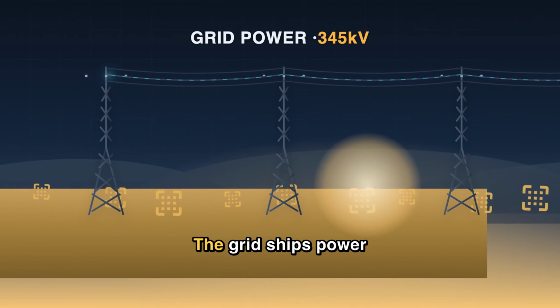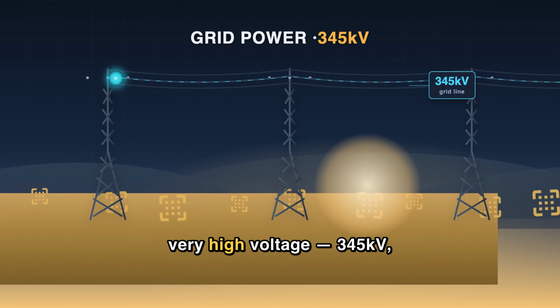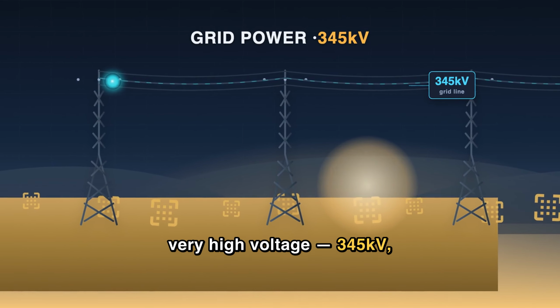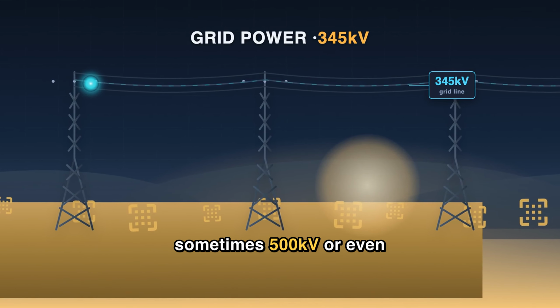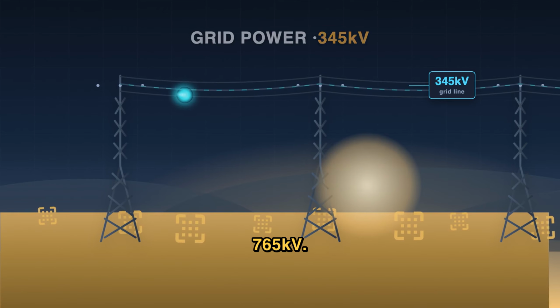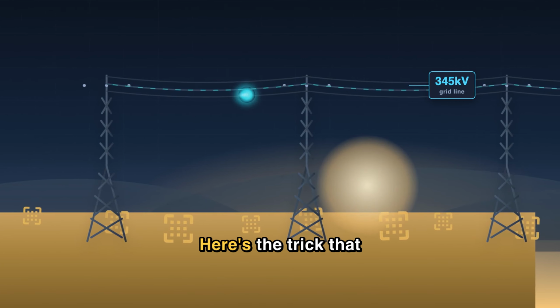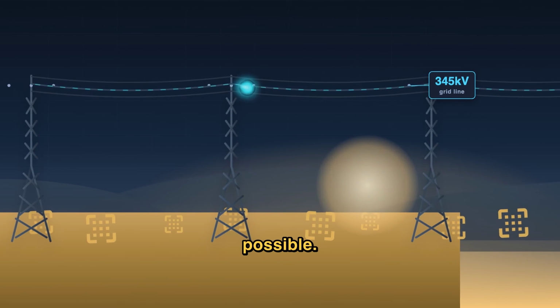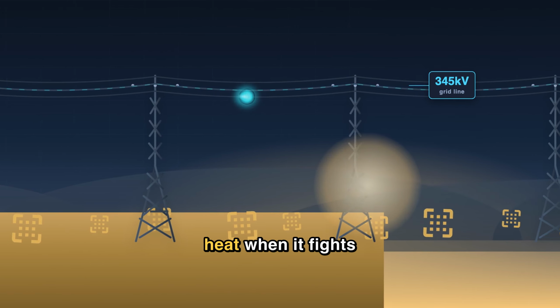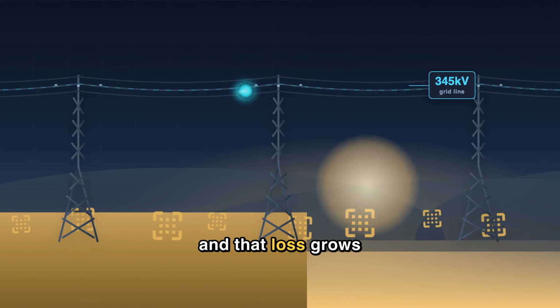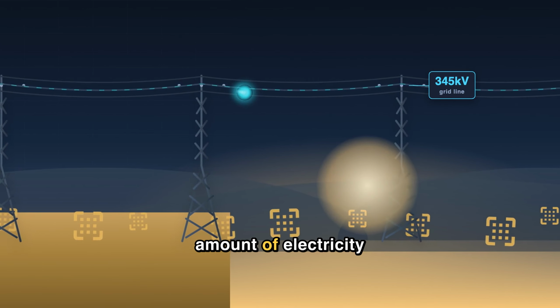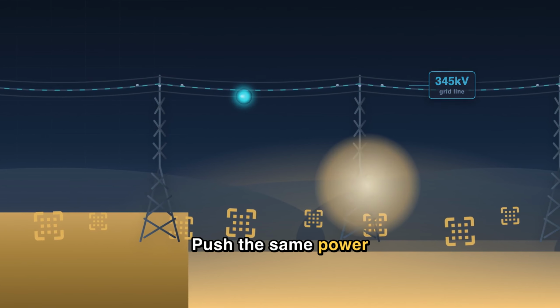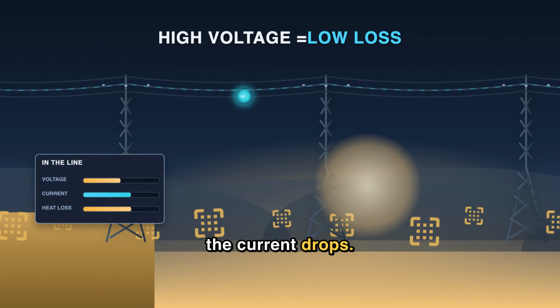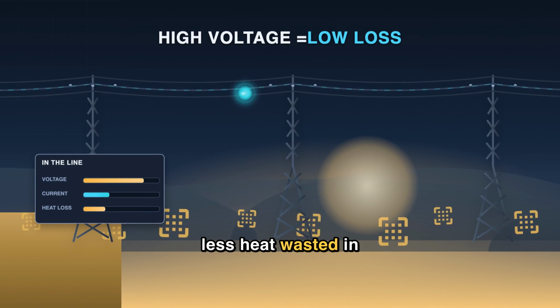Start at the top. The grid ships power to the campus at very high voltage, 345 kilovolts, sometimes 500 kilovolts or even 765 kilovolts. Why so high? Here's the trick that makes long-distance power possible. Electricity loses energy as heat when it fights its way through wires, and that loss grows with the current, the amount of electricity flowing. Push the same power at higher voltage and the current drops. Lower current means far less heat wasted in the line.